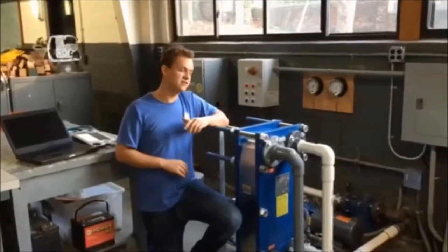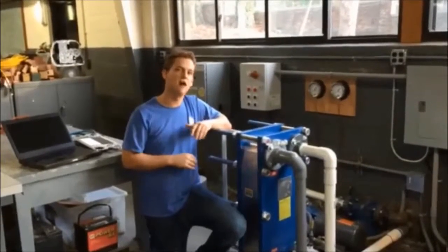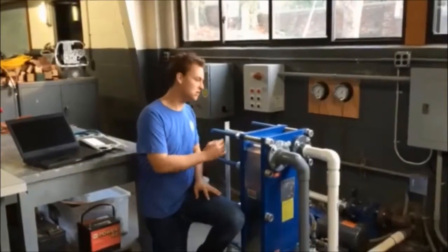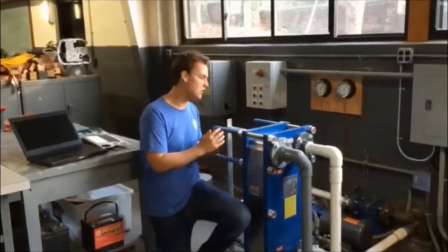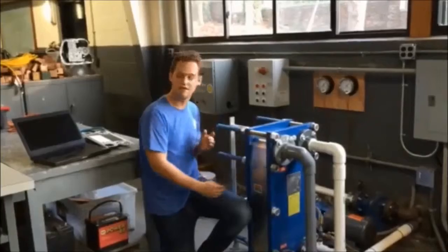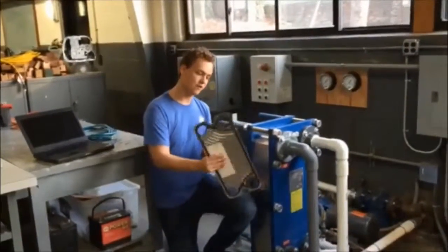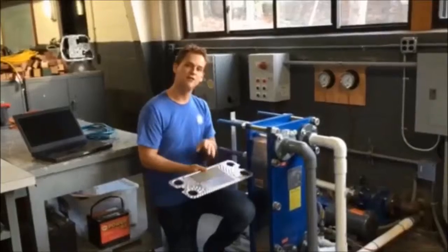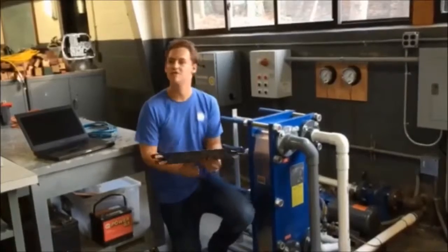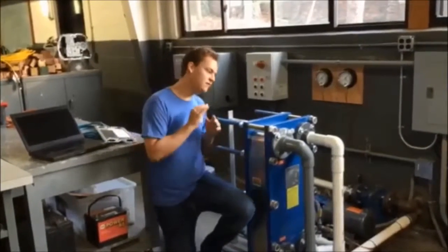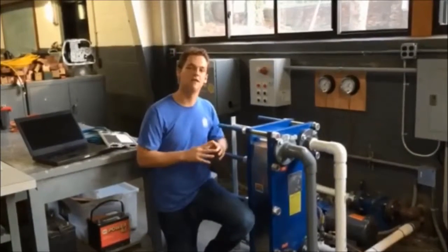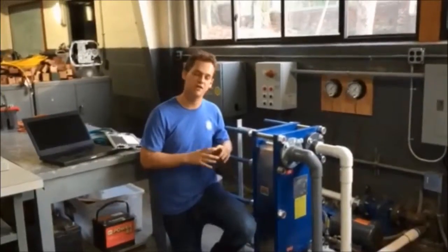In addition to the advantage of being able to remove and add plates to achieve the correct level of heat exchange, the nature of the plate-type heat exchanger also allows for ease of cleaning in a very small space. You only need this much distance to remove your plates and clean them or replace them if necessary. And these little plates are pretty thin, there's not much mass to them, so they're pretty cheap. And you can store lots of spares on board without taking up too much space or adding too much weight. This is one of the distinct advantages of the plate-type heat exchanger over a shell and tube, where you need twice the length of the shell and tube heat exchanger to remove tubes to replace or clean them.